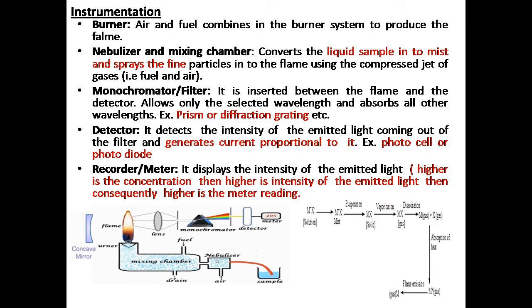Depending on the intensity of the emitted light, the detector — a photocell or photodiode — detects the intensity of the light coming out of the monochromator. It generates a current whose magnitude is directly proportional to the concentration of the solution. Higher concentration means higher current and a higher meter reading. This is the overall instrumentation of flame photometry.